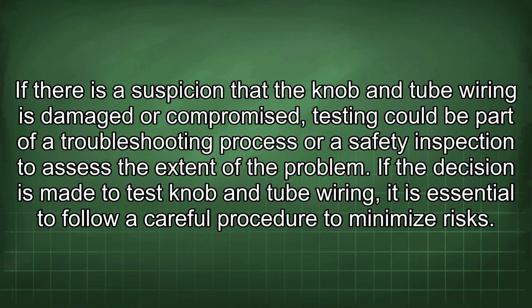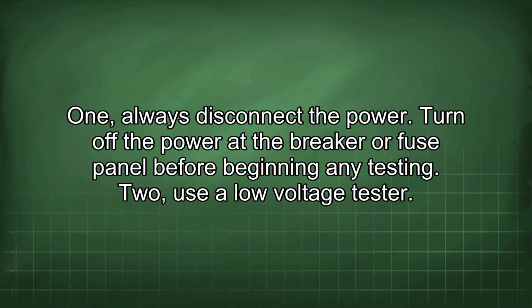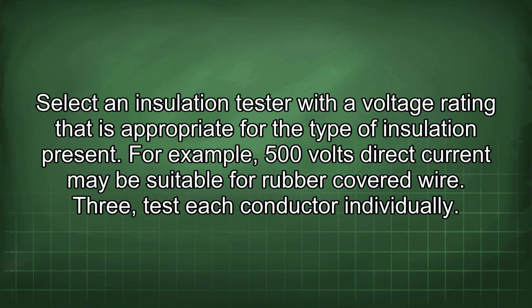If the decision is made to test knob and tube wiring, it is essential to follow a careful procedure to minimize risks. 1. Always disconnect the power. Turn off the power at the breaker or fuse panel before beginning any testing. 2. Use a low voltage tester. Select an insulation tester with a voltage rating that is appropriate for the type of insulation present. For example, 500 volts direct current may be suitable for rubber-covered wire.